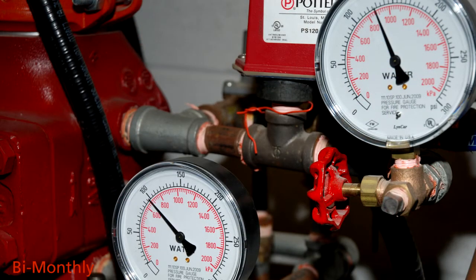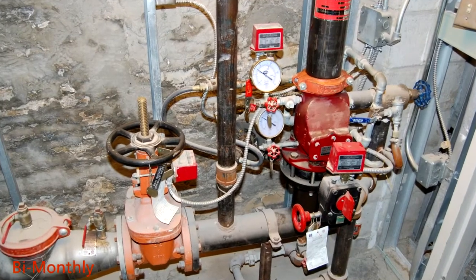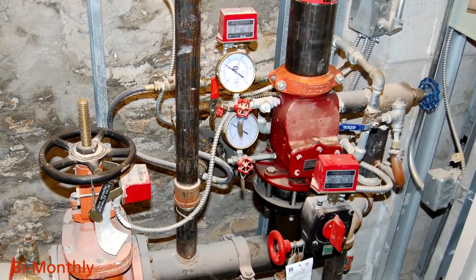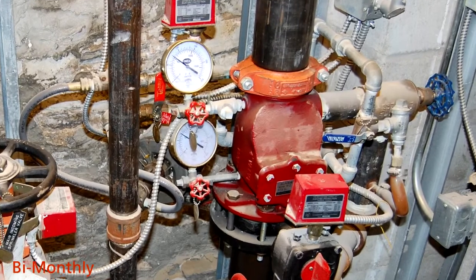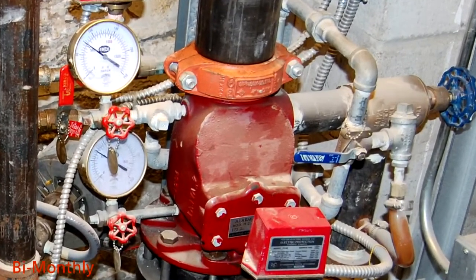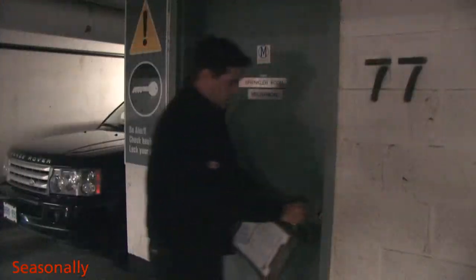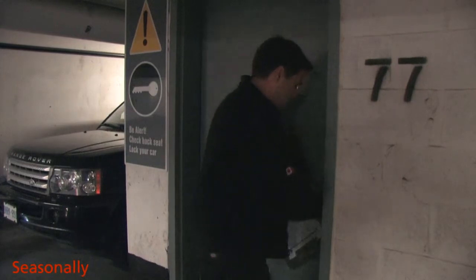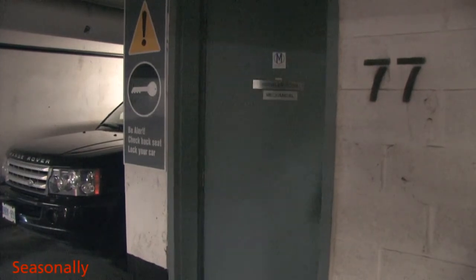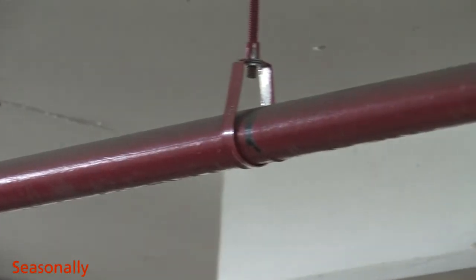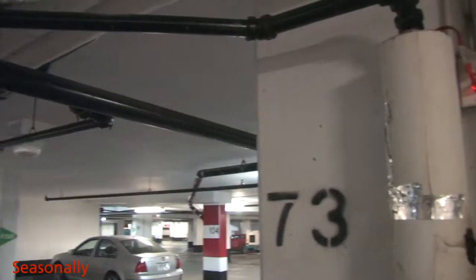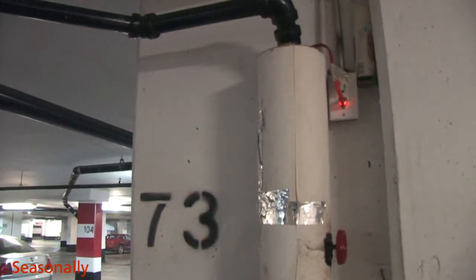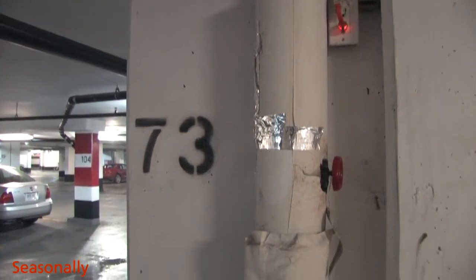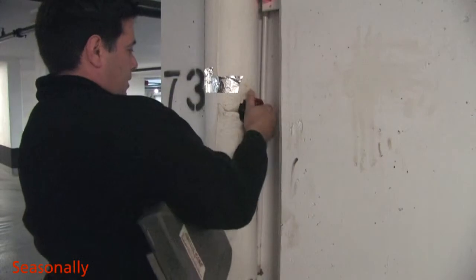On a bi-monthly basis, check the sprinkler control valves to ensure the pressures are in optimal range. If applicable, priming water levels for dry pipe valves must be maintained at the proper level. Any problems must be reported to your local fire department. Sprinkler systems in parking garages are usually pressurized with air instead of water to avoid freezing. With changing temperatures, however, condensation can produce small amounts of water in the pipes. This water should be removed by using special draining stations like this one, normally twice a year in the spring and fall.